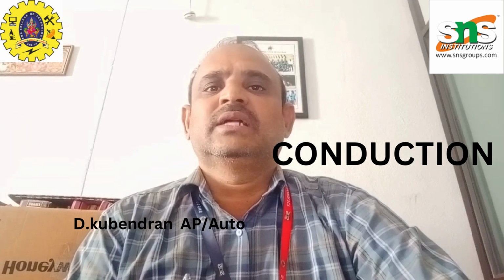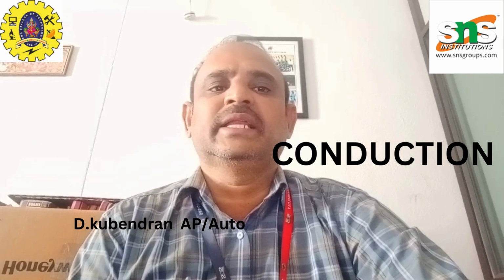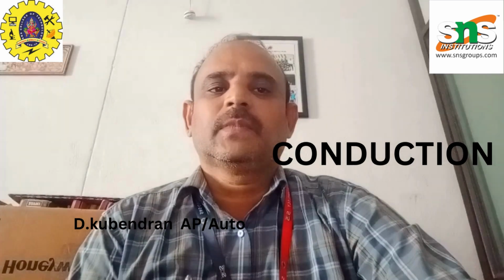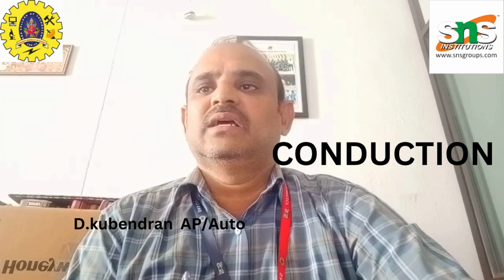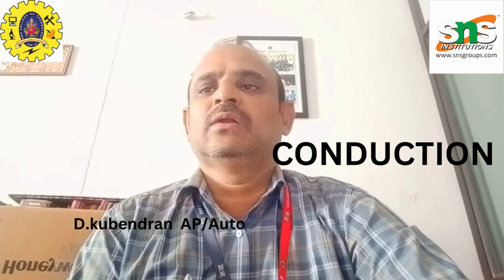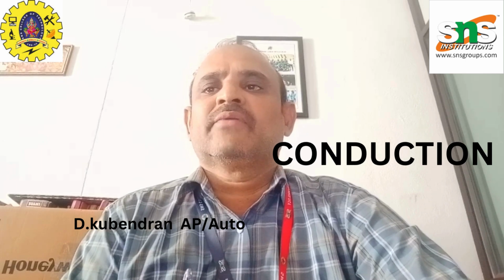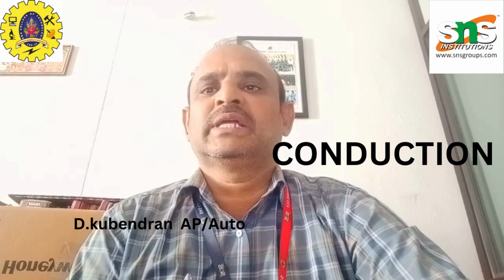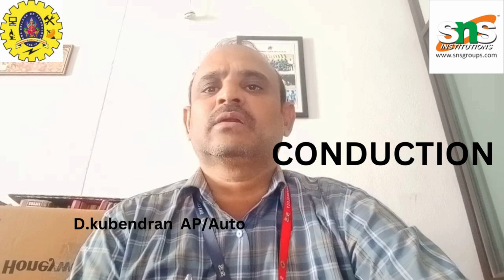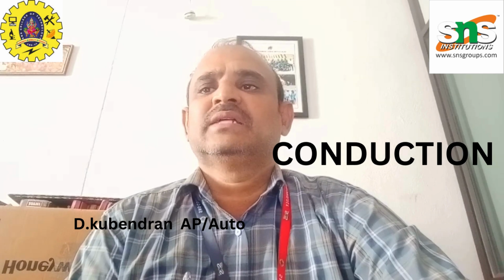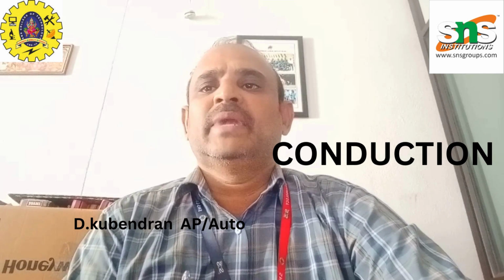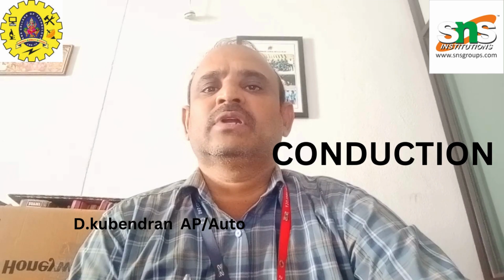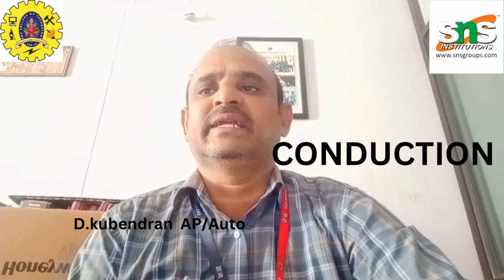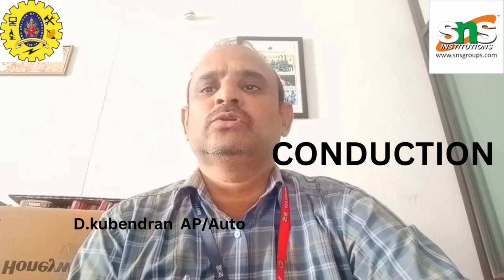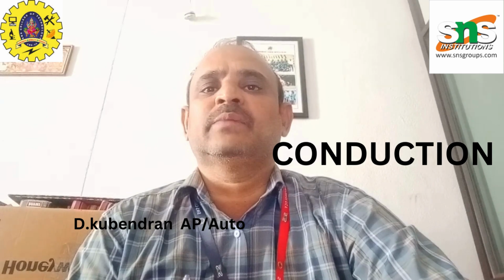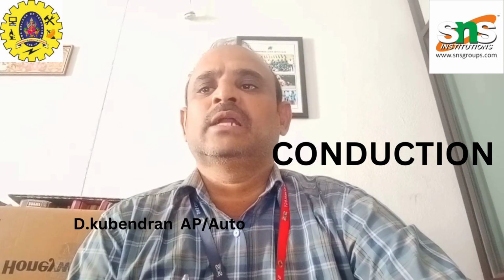There are essentially three types of insulating materials. One is fibrous, second one is cellular, third one is granular. Fibrous means small diameter particles or fibers loosely filled in the gap between surfaces to be insulated. Mineral wool is one such material for temperatures below 700 degrees centigrade. Fiberglass insulation is used below 200 degrees centigrade.